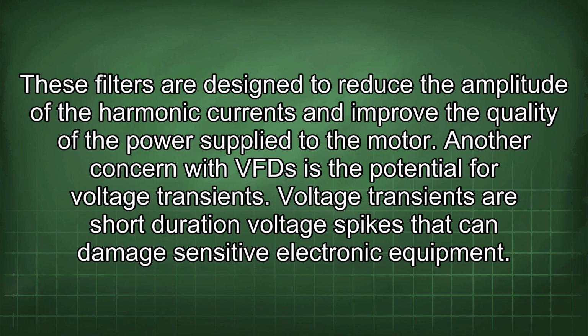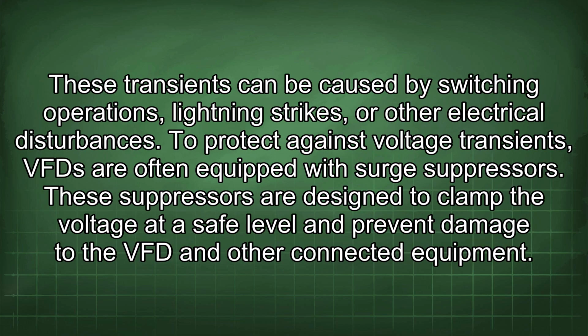to the motor. Another concern with VFDs is the potential for voltage transients. Voltage transients are short-duration voltage spikes that can damage sensitive electronic equipment. These transients can be caused by switching operations, lightning strikes, or other electrical disturbances. To protect against voltage transients, VFDs are often equipped with surge suppressors.